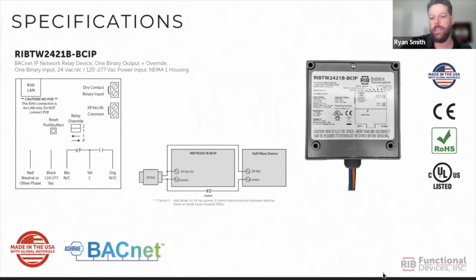You can also see the low voltage power connection, 24 volts AC or DC, as well as a dip switch for relay override and the button to return to default settings. The wiring from the bottom of the relay includes the common, normally open, normally closed connections, as well as connections to power the device with 120 to 277 volts AC if your application requires that.